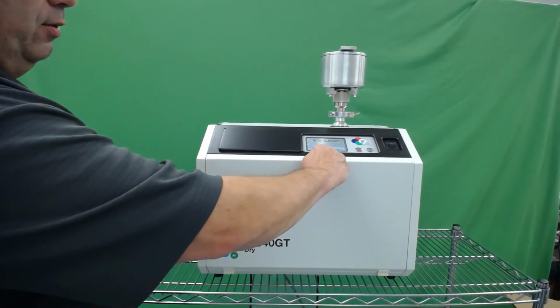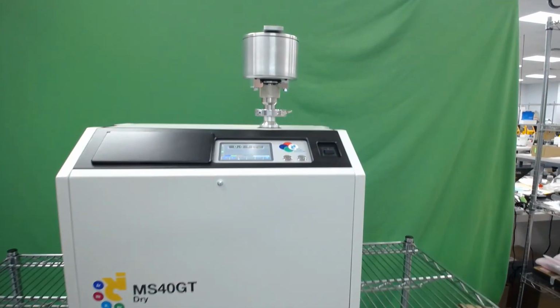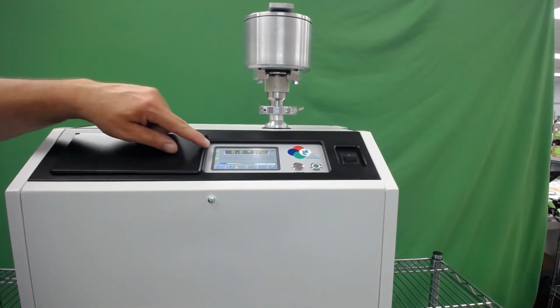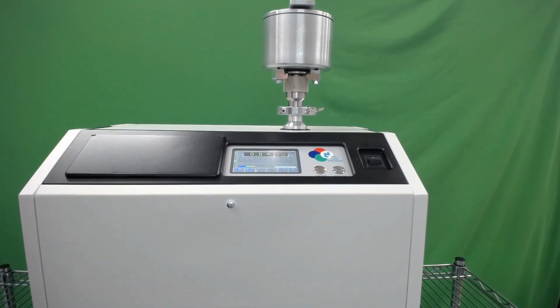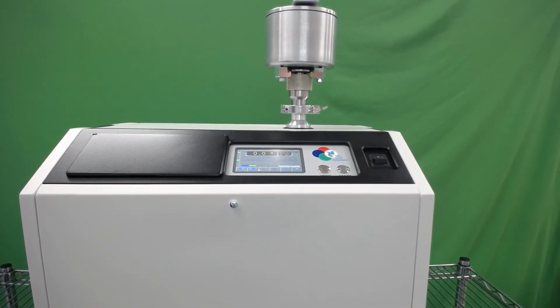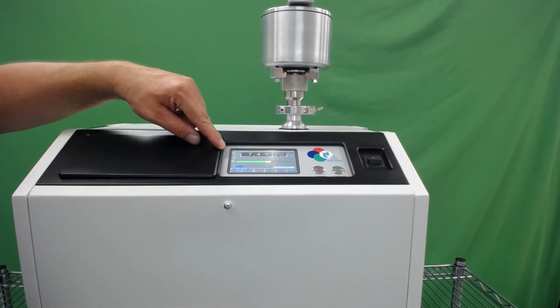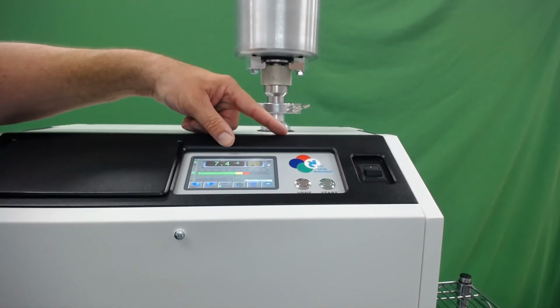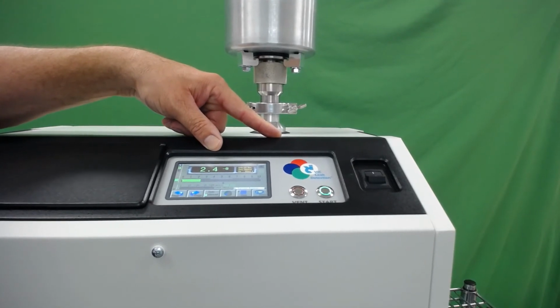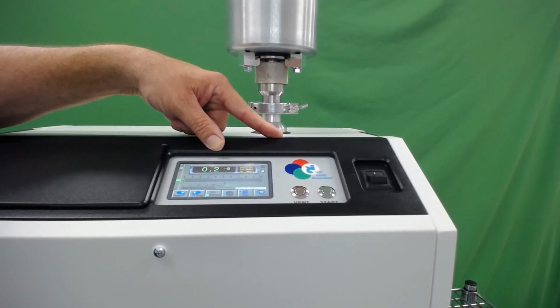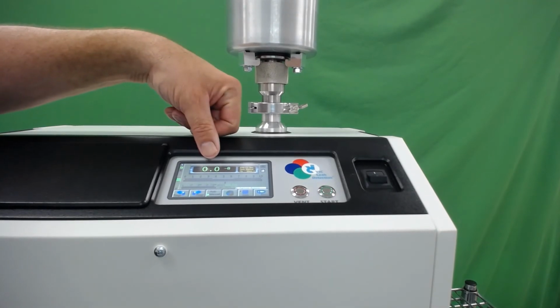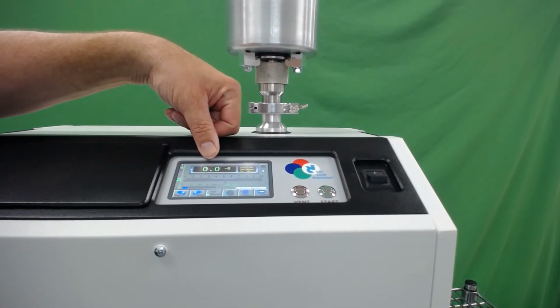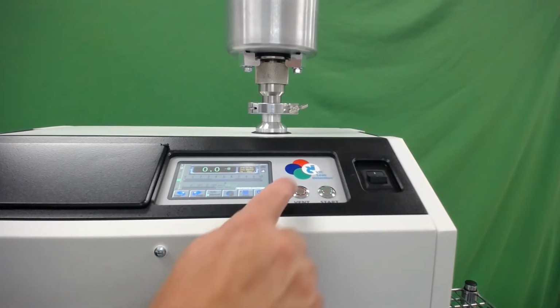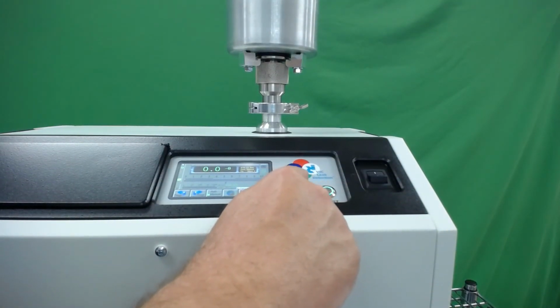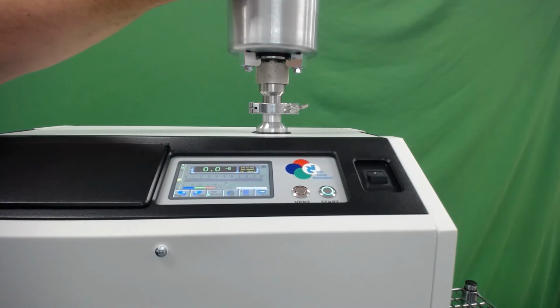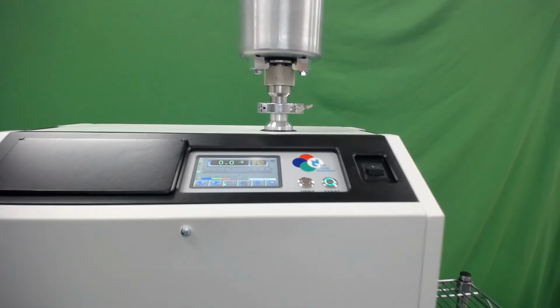The test port will begin to evacuate, and once the desired vacuum level is achieved, the machine will go into a direct testing mode. Okay. The machine is now in reverse testing, and you'll see that the leak rate will start cleaning up, allowing us to continue pumping down further. If the product was actually in the chamber and leaking, we would get an indication of what the desired leak rate is. By pressing and holding the vent button, the test cup is now vented to atmosphere. It can be opened and the product removed.